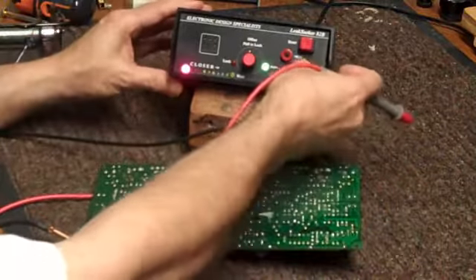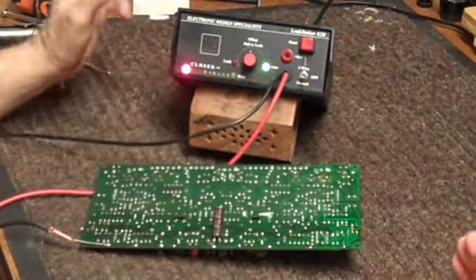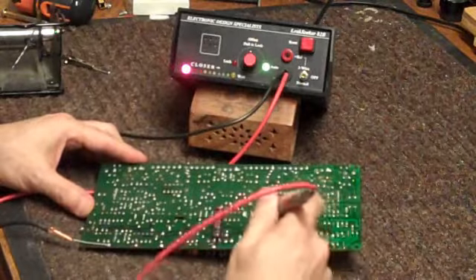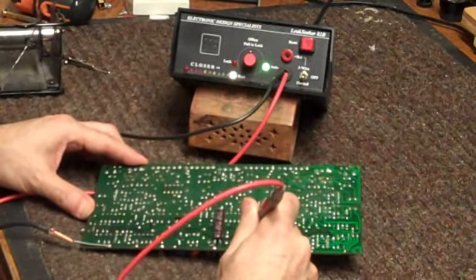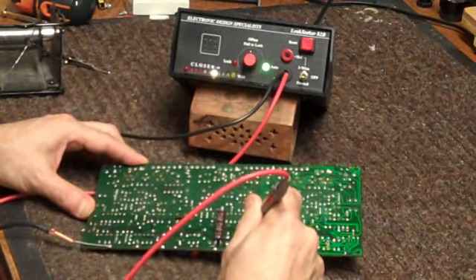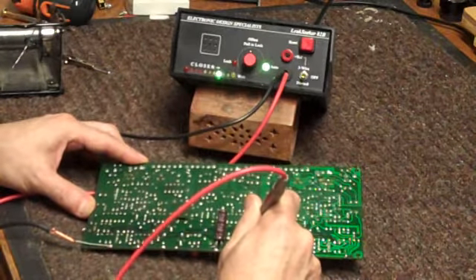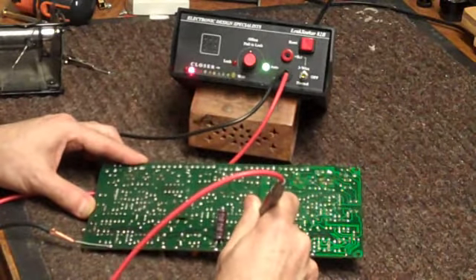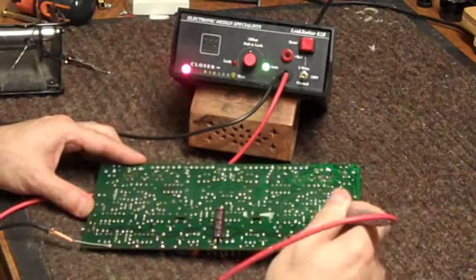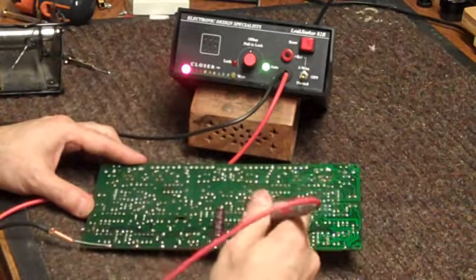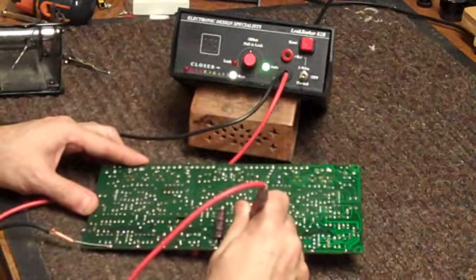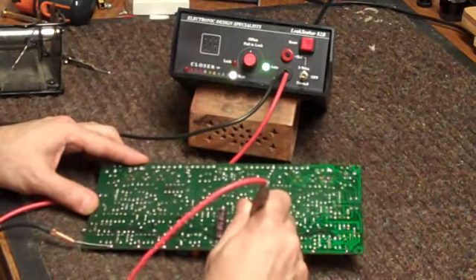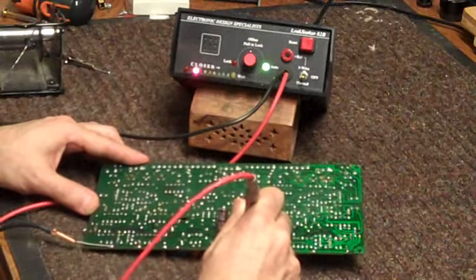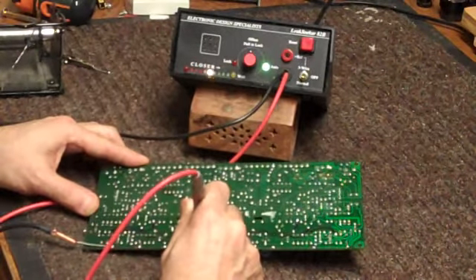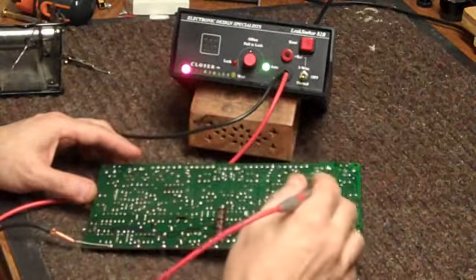If we start as a normal test, black lead to ground, 2-wire test, push for a new test, and go anywhere along this lead, we get all kinds of weird readings. The reason is that every time we put the test lead on, this capacitor is trying to charge up. So wherever you go, it's going to be near impossible because it's not a steady tone.